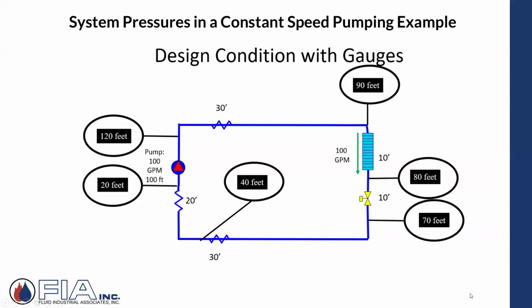So if someone was to put gauges around the system, in this case, for easy numbers, I'm pumping 100 GPM and overcoming 100 feet of pressure drop. Then I just assign different pressure drops for terminal units, piping, coils, the control valve, more piping. I come back to the suction of my pump, and I still have my control head of 20 feet. I'm adding 100 feet of pump head. So suction is 20, discharge is 120. That's a stated set of conditions.